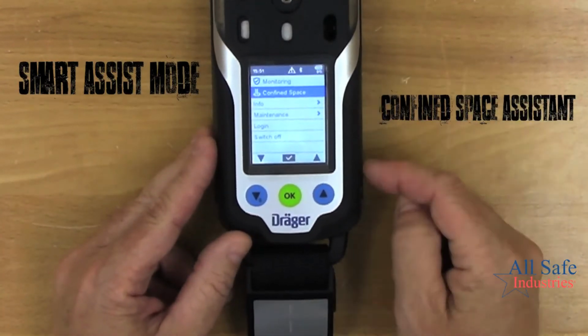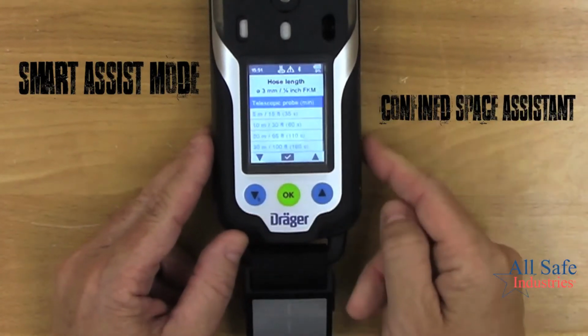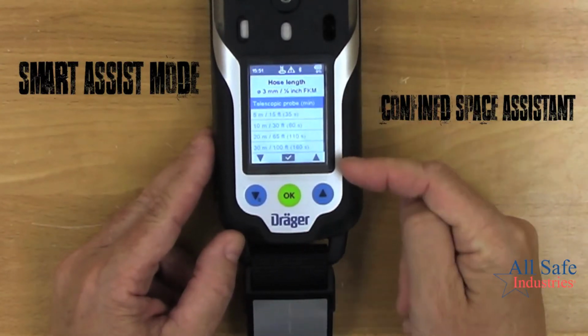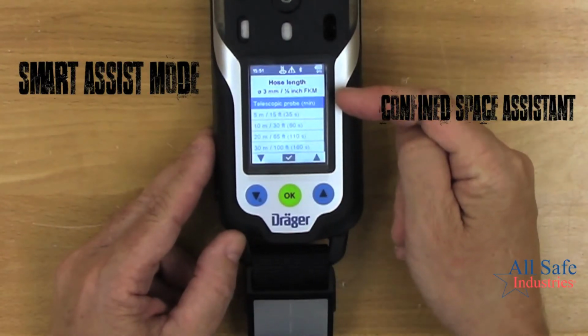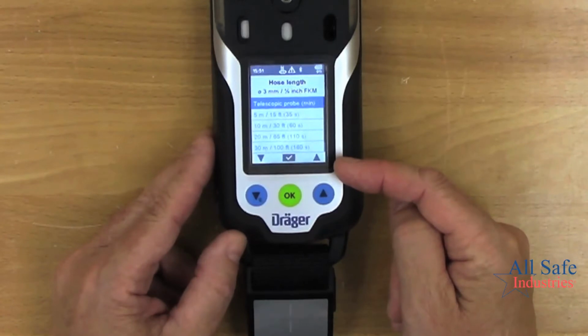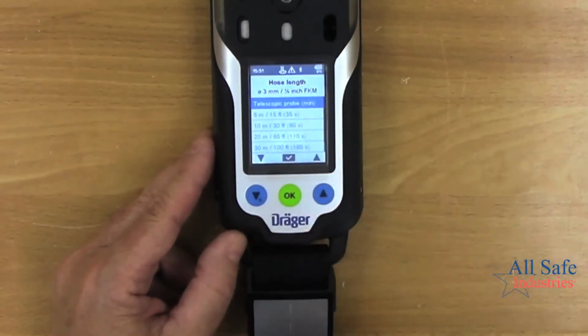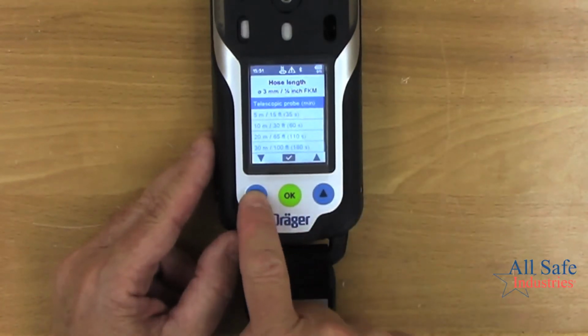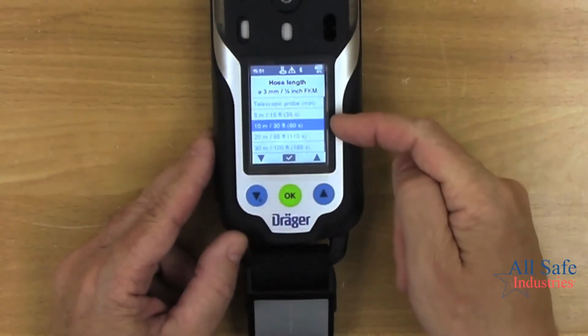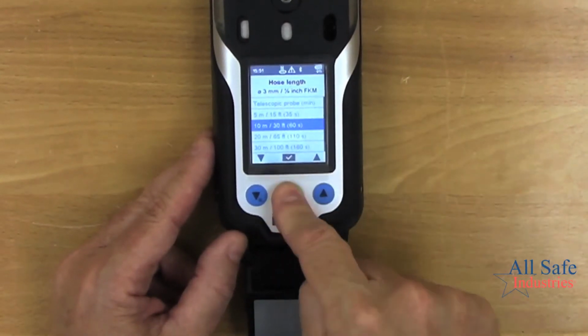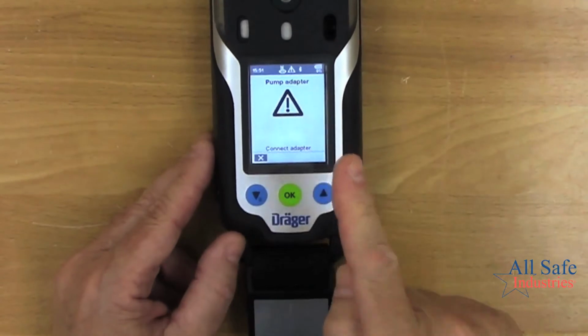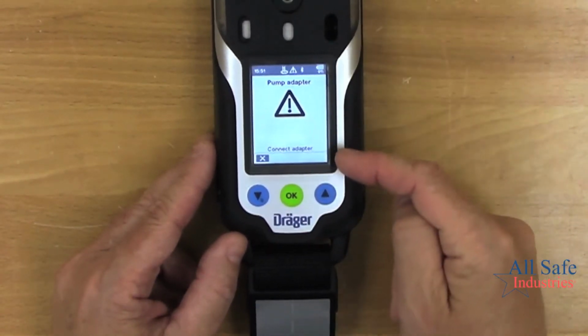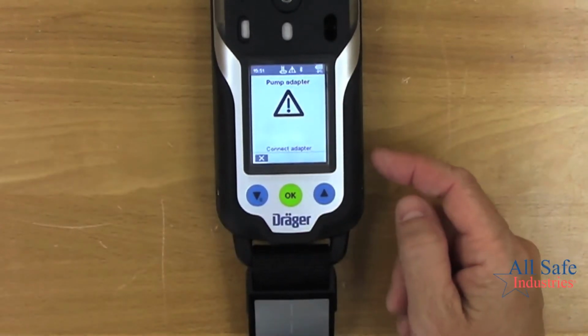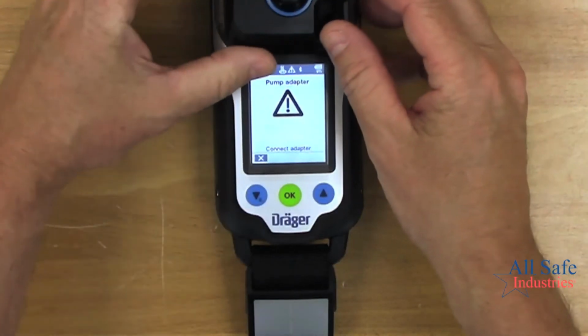If I drop down to confined space and hit OK, it asks if I'm using a probe or a set amount of tubing. Let's say I'm using 30 feet of tubing today. I drop down to 30 foot of tubing, hit OK, and it warns me that I haven't attached my pump yet, so I need to bring my pump cap over and screw it into place.